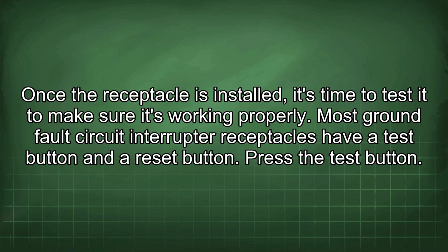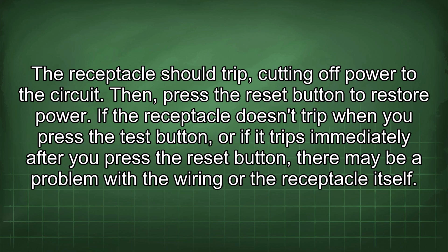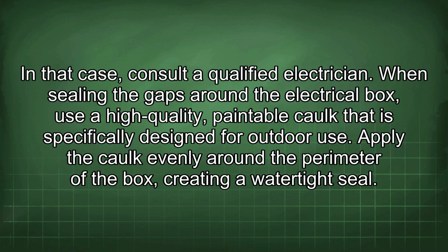Once the receptacle is installed, it's time to test it to make sure it's working properly. Most ground fault circuit interrupter receptacles have a test button and a reset button. Press the test button. The receptacle should trip, cutting off power to the circuit. Then press the reset button to restore power. If the receptacle doesn't trip when you press the test button, or if it trips immediately after you press the reset button, there may be a problem with the wiring or the receptacle itself. In that case, consult a qualified electrician.